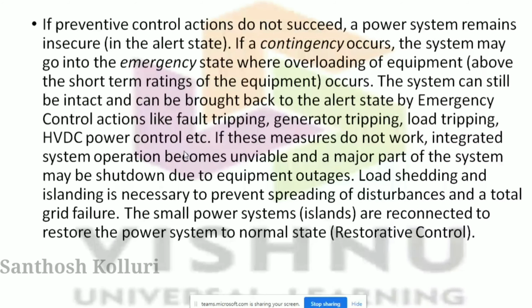If preventive control actions do not succeed, a power system remains insecure or in the alert state. If a contingency occurs in the system, it may go into the emergency state where overloading of equipment occurs. The system can still be intact and can be brought back to the alert state by emergency control actions like fault tripping, generator tripping, load tripping, HVDC power control, etc. If these measures do not work, integrated system operation becomes unviable, and a major part of the system may be shut down due to equipment outages. Load shedding and islanding are necessary to prevent the spreading of the disturbances and total grid failure. The small power systems like islands are reconnected to restore the power system to the normal state, or restorative control.